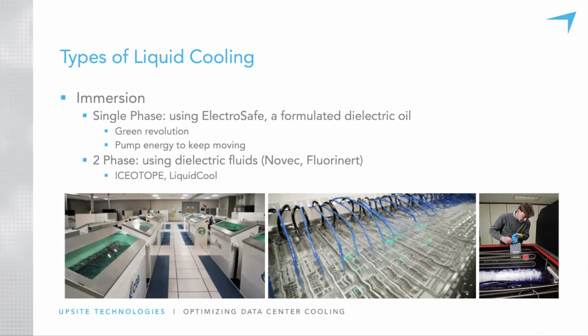In this two-phase solution, normally this lid would be closed and this gas would just be condensing on the coils and dripping back into the tank. There's some benefits to this. Every component that is sitting in the tank, 100% of the heat is picked up by the liquid, but it uses up more floor space. It's messy in some cases. A lot of people having experience with this experience the mess being a particular challenge. And the liquid, if it's the more viscous oil-based solutions, requires a significant amount of energy to distribute that liquid around through the tank. You need to keep that liquid moving or components will overheat.